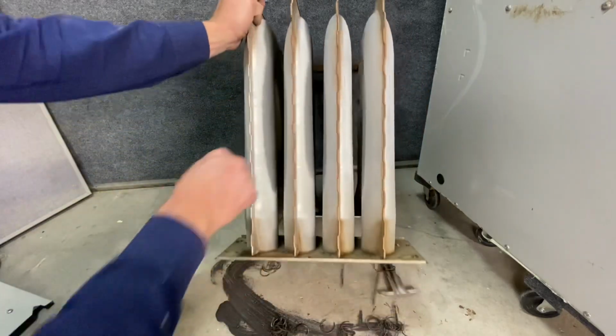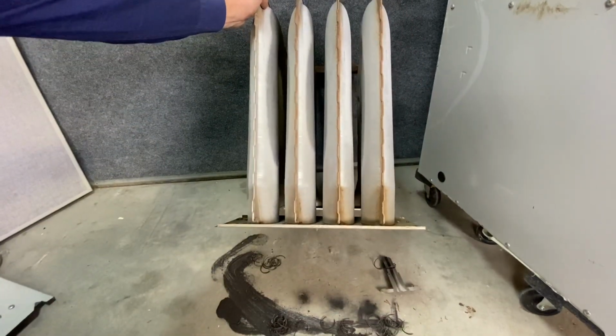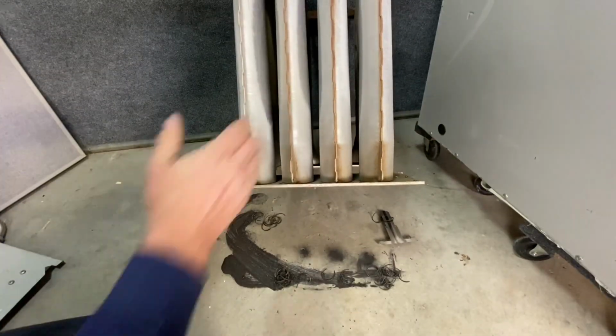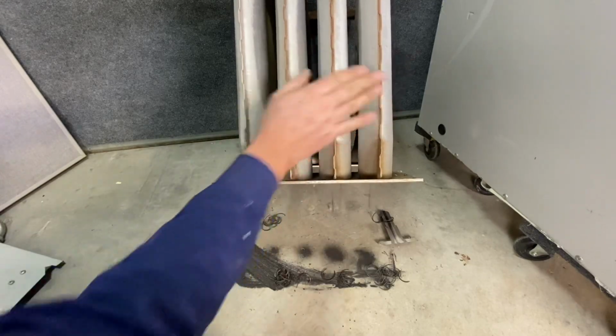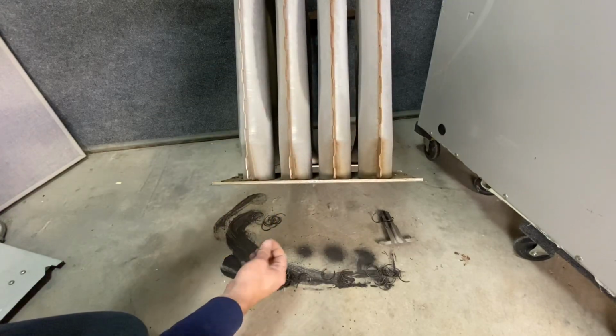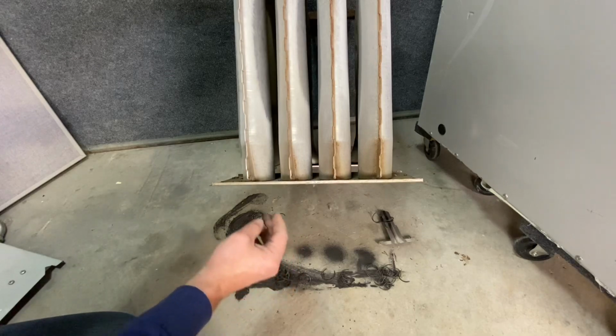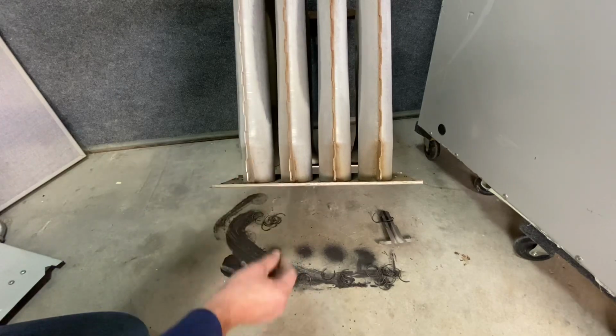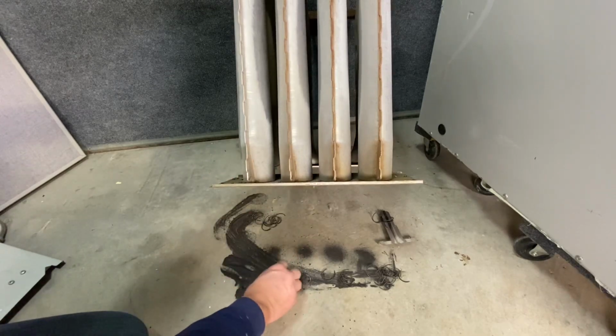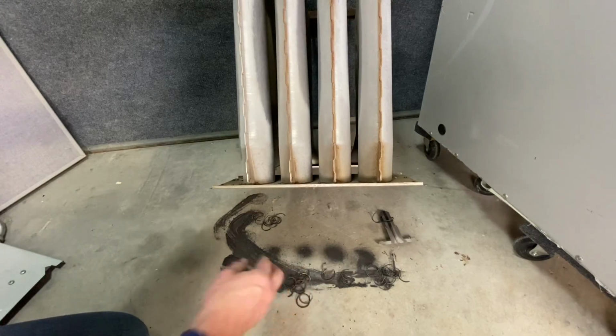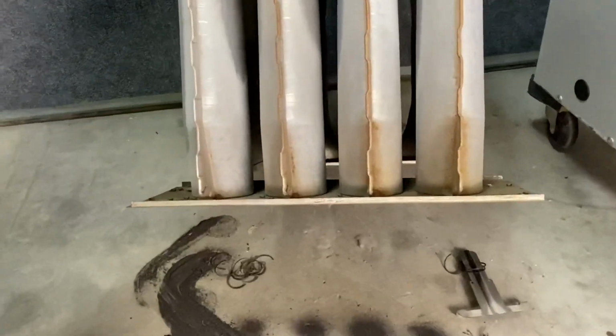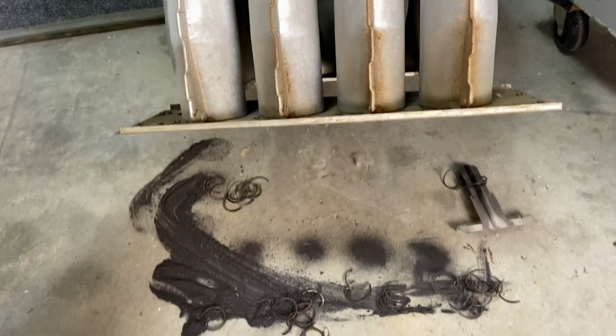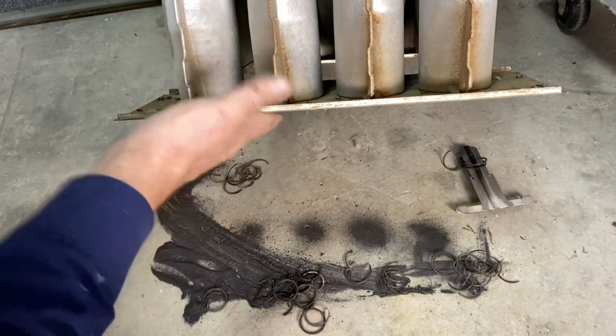As I turn this upside down, you can see that tons and tons of rust and stuff just keep falling out of this furnace. You've got to think that this is the material that keeps the flames separate from the air in the house, and that's part of the heat exchanger itself, and it's just completely rusted up and in really, really bad shape. So it's a really good thing that they changed out this furnace, because it was done.